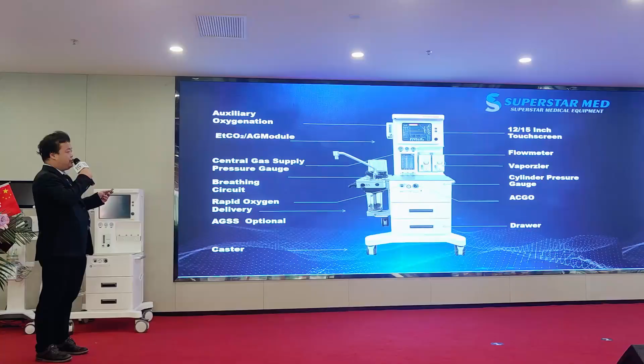For the features of this NCS system, we now have 12, 15, and 18 inch models, and all of them come standard with a touch screen. For the flow meter, we have a choice: you can use the mechanical one or the digital one. It meets different requirements from hospitals and tenders. For the vaporizer, we are still using a 2 vaporizer design, and you can choose from halothane, enflurane, isoflurane, and sevoflurane. I also want to mention that some high-end hospitals now require desflurane. For the desflurane vaporizer, in China we don't have a manufacturer, but we can ensure that if you buy the desflurane vaporizer from your local supplier, you can equip it on our machine. That is not a problem.